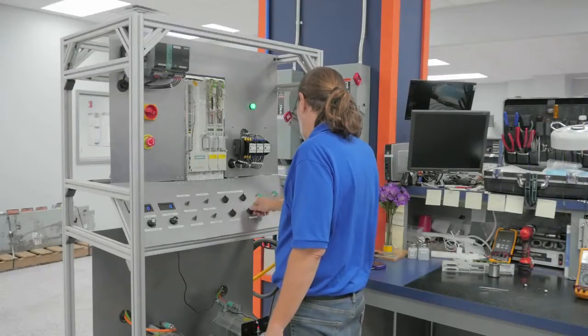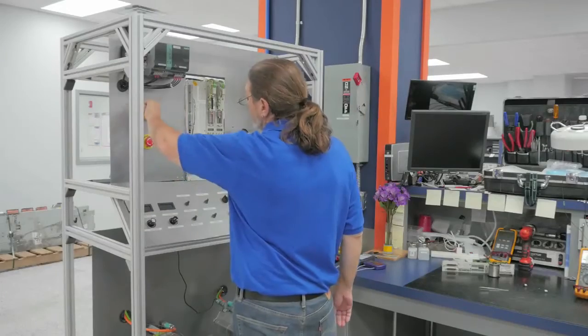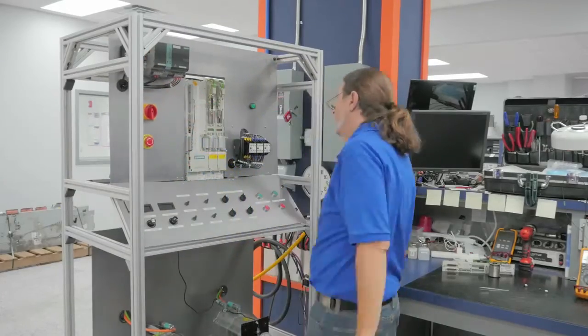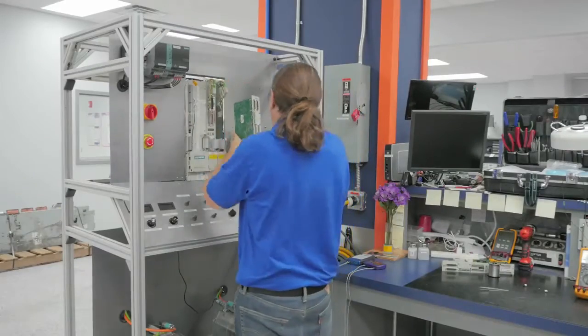Without the use of our custom test stand to actually function test the servo card, the unit could have shipped out to the customer repaired as just powering up the card on a bench after changing the capacitors would have indicated the problem was resolved.